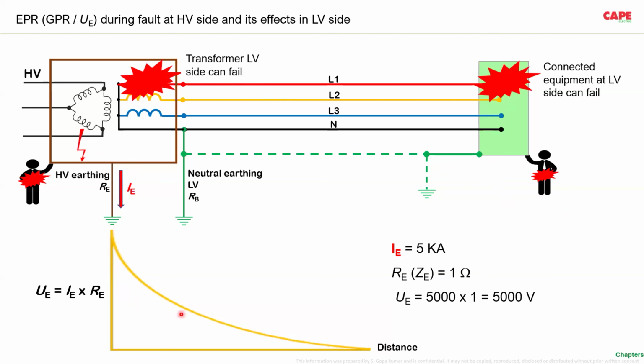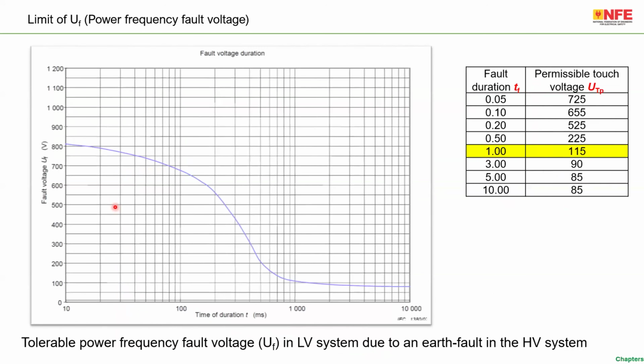It is all because of this potential gradient, the EPR or the GPR, which is created because of the fault current flow to the earth electrode. The limits of the maximum touch voltage in any location, irrespective of high voltage or low voltage, depending upon the disconnection time, are given here.